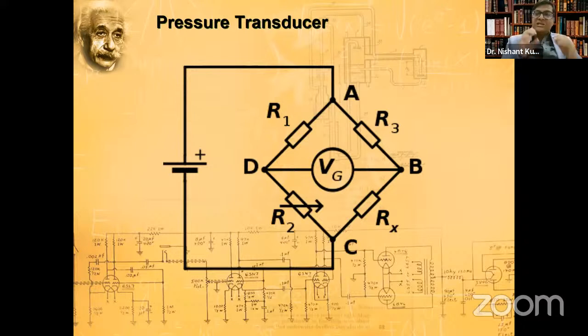Now remember, any change in pressure will produce a change in resistance, which will lead to a flow of current. So R1 and R3 are known. R2 we calibrate with the pressure: we open it to air and zero it. Then when we connect it to the arterial line, depending on the pressure, it is simply given by the formula R2 by R1 equals Rx by R3. Now we know R1, R3 and R2, so Rx is calculated.